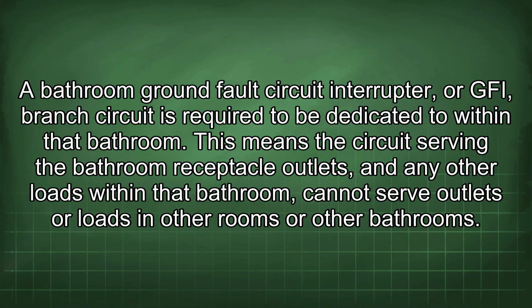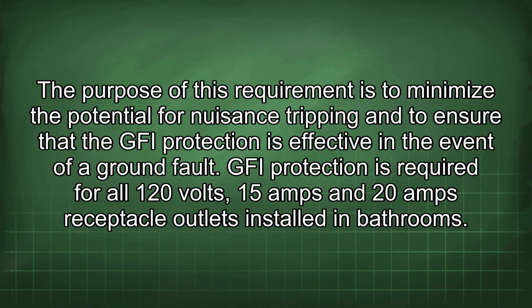A bathroom ground fault circuit interrupter, or GFI, branch circuit is required to be dedicated to within that bathroom. This means the circuit serving the bathroom receptacle outlets and any other loads within that bathroom cannot serve outlets or loads in other rooms or other bathrooms. The purpose of this requirement is to minimize the potential for nuisance tripping and to ensure that the GFI protection is effective in the event of a ground fault.